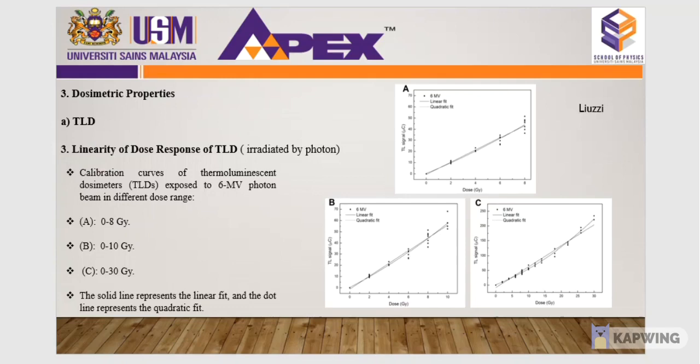However, the calibration conditions such as field size, beam energy, angle of beam incidence, and air gap may indeed affect the calibration curve and dose response. As a result, those factors and their effect should be assessed in order to obtain a more complete description of the TLD performance.